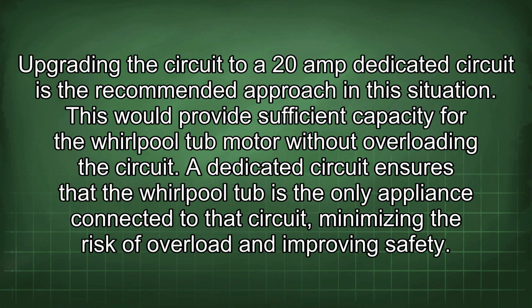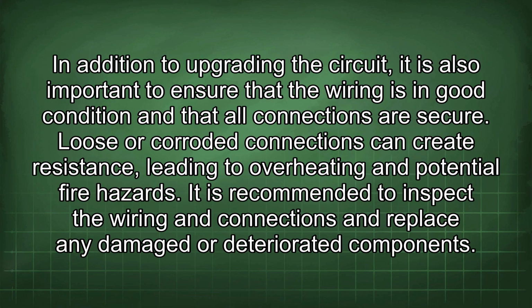A dedicated circuit ensures that the Whirlpool tub is the only appliance connected to that circuit, minimizing the risk of overload and improving safety. In addition to upgrading the circuit, it is also important to ensure that the wiring is in good condition and that all connections are secure. Loose or corroded connections can create resistance, leading to overheating and potential fire hazards. It is recommended to inspect the wiring and connections and replace any damaged or deteriorated components.